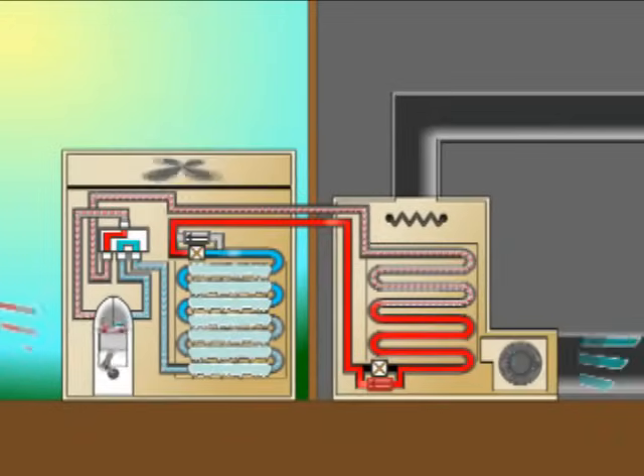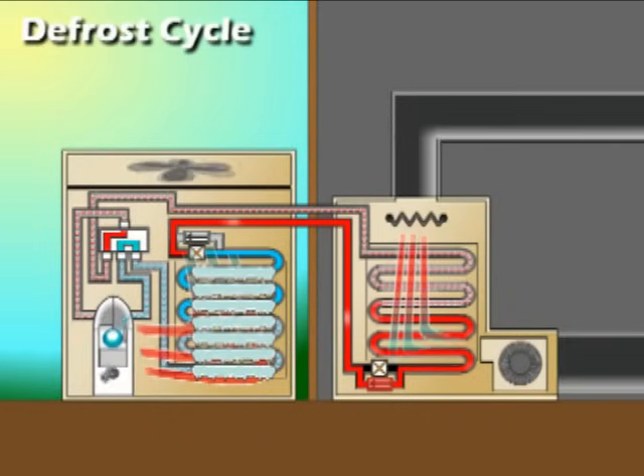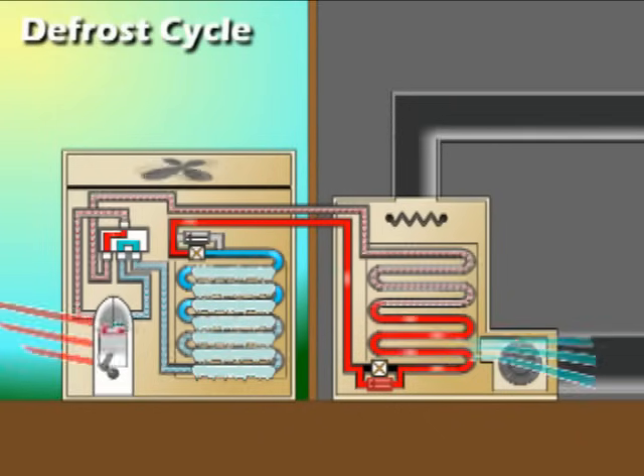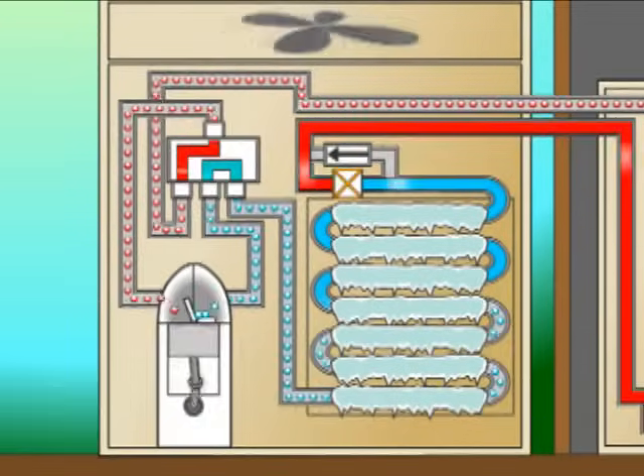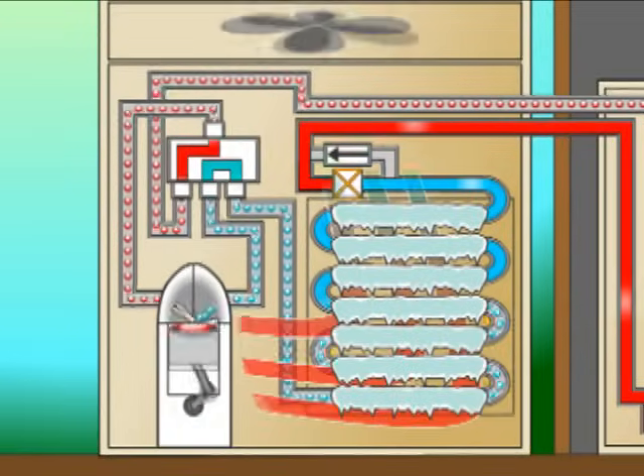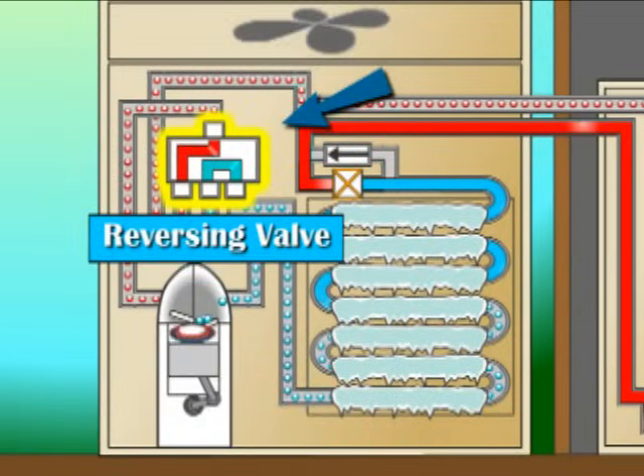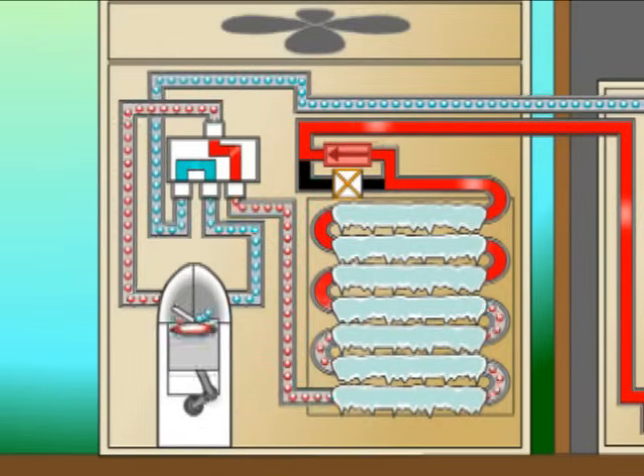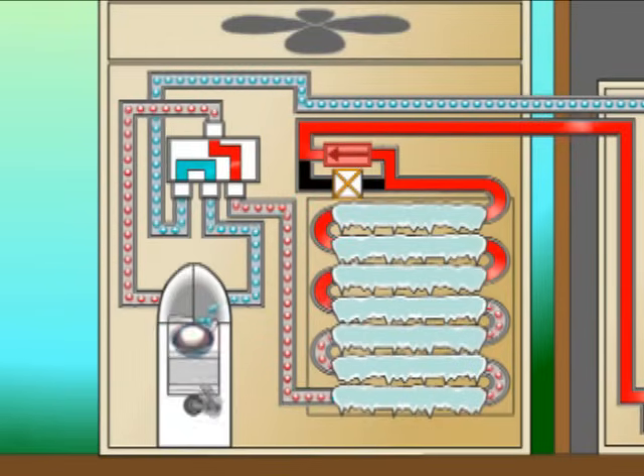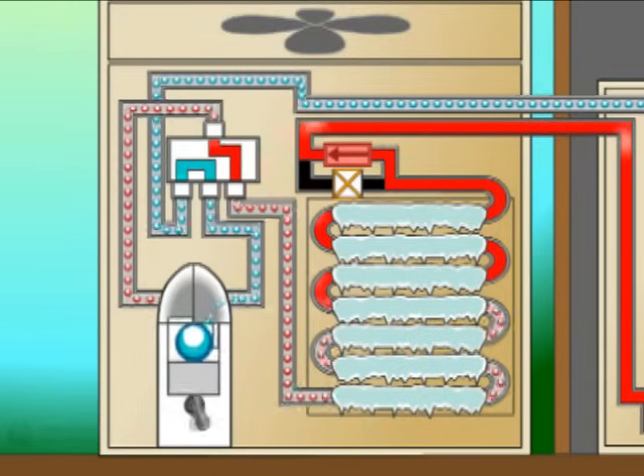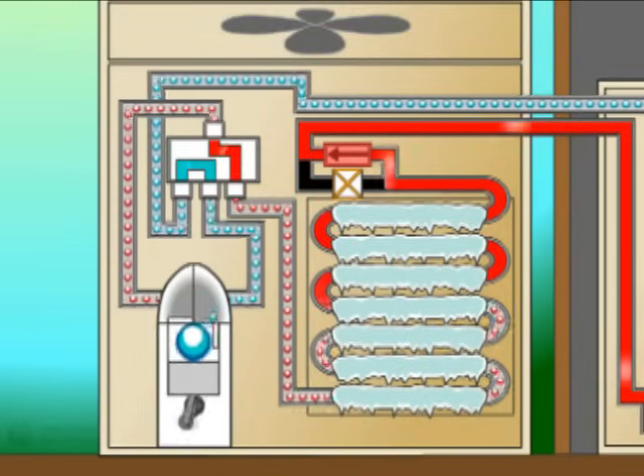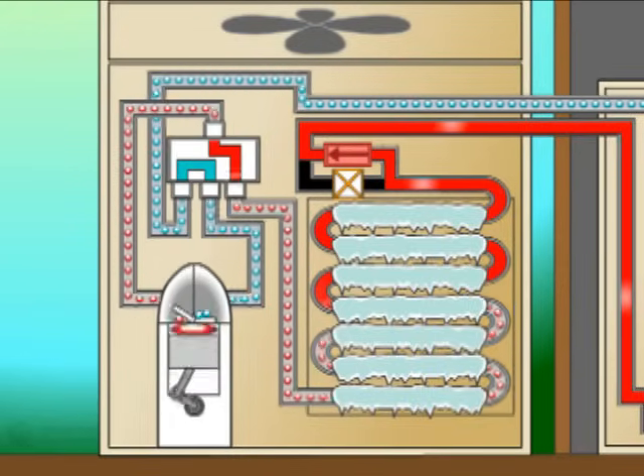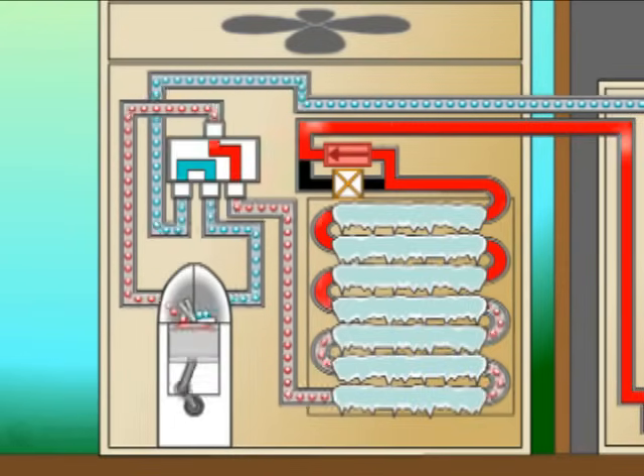This very low operating temperature allows ice or frost to accumulate on the outside of the evaporator. The remedy: the defrost cycle. As the defrost cycle is initiated, the reversing valve switches the refrigerant path back to that of the summer mode. This allows indoor heat to be transferred from the inside air stream to the outside coil, thereby melting the accumulated frost.